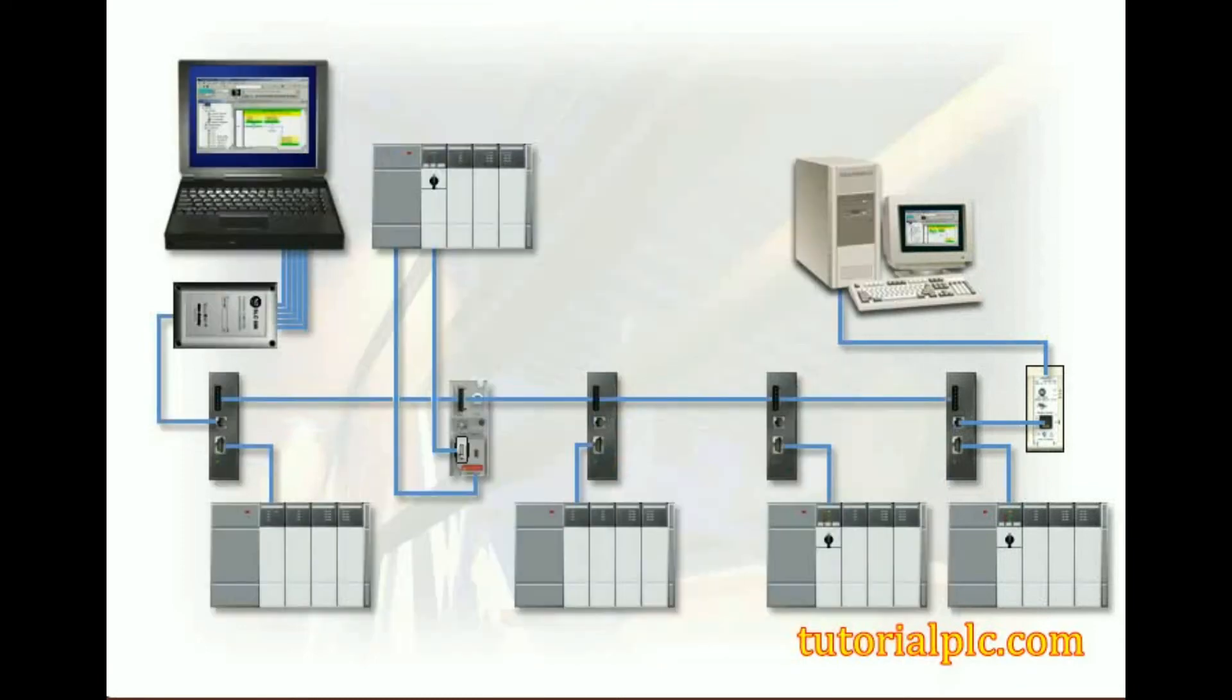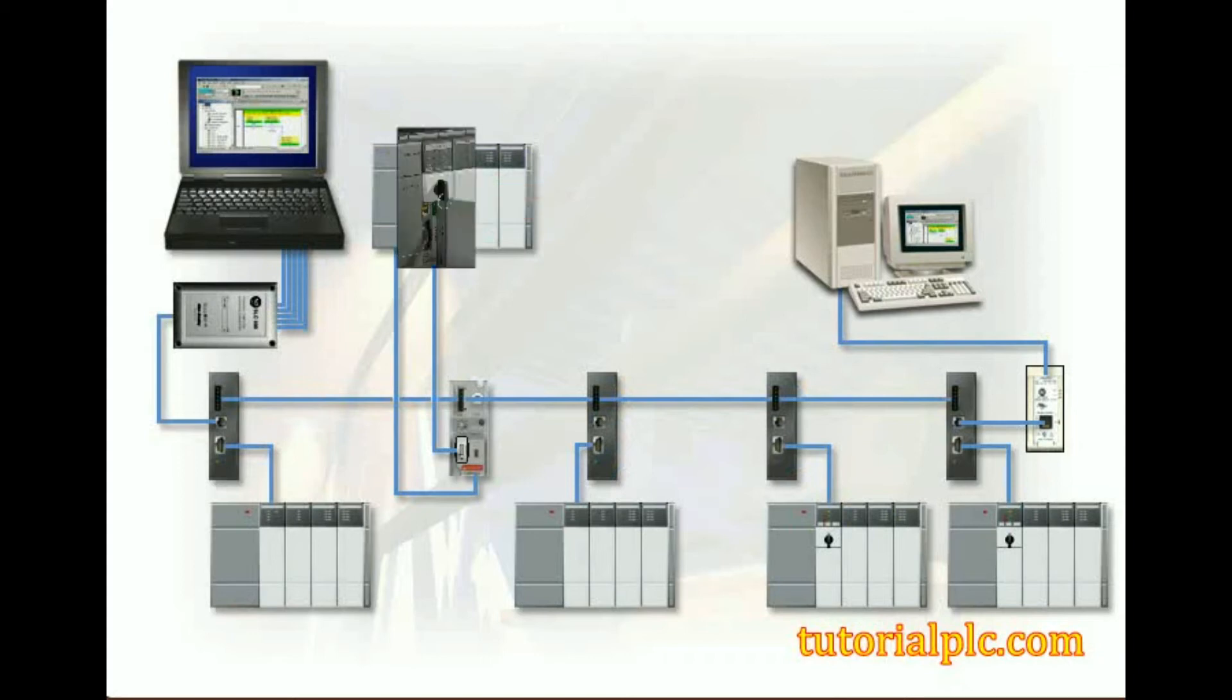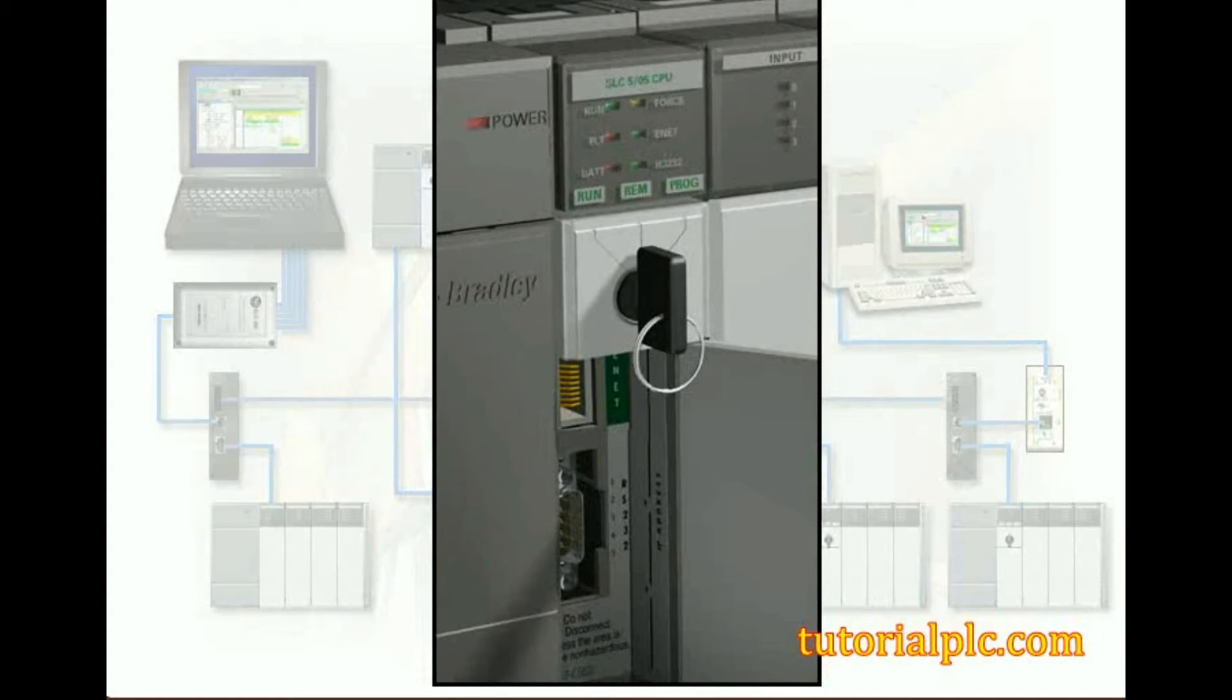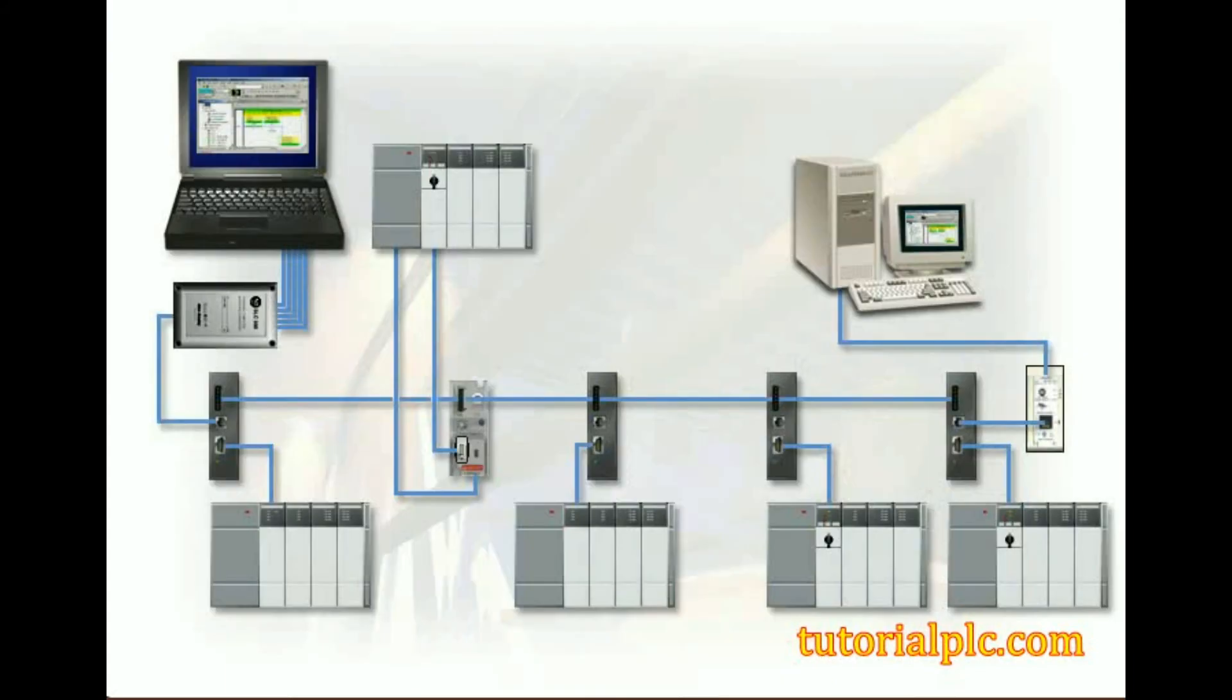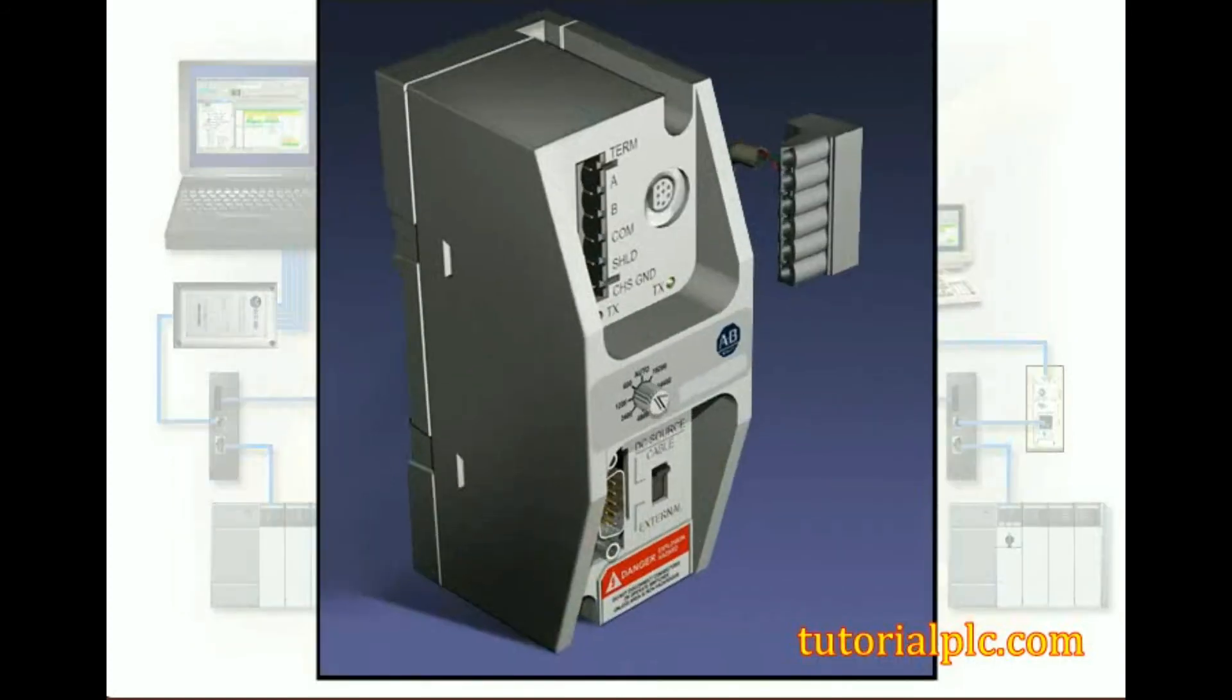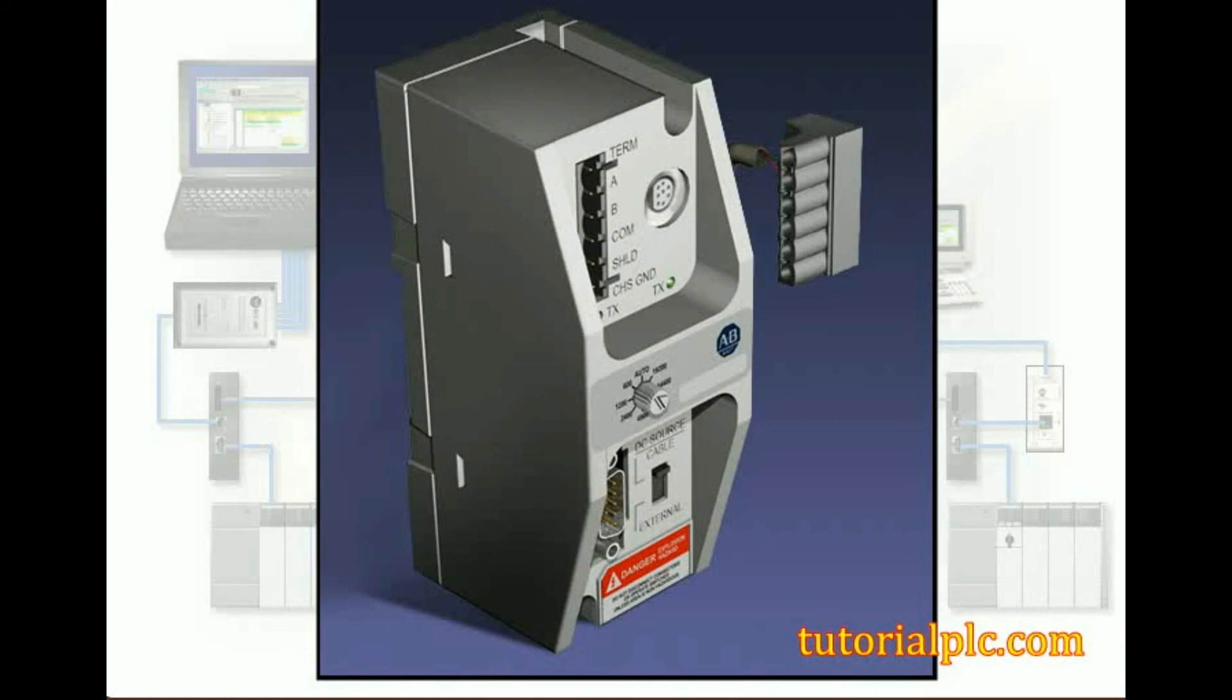Let's say we're adding an SLC 5/05 processor to our plant, which has an existing DH-485 network. An SLC 5/05 processor doesn't have onboard DH-485 connectivity capabilities. So to use a DH-485 network to communicate to an SLC 5/05 processor, we can use an AIC-plus advanced interface module. An AIC-plus module converts an RS-232 serial interface to DH-485, but unlike a UIC module, it can be internally or externally powered. Like a UIC module, an AIC-plus module allows direct connectivity to a DH-485 network.